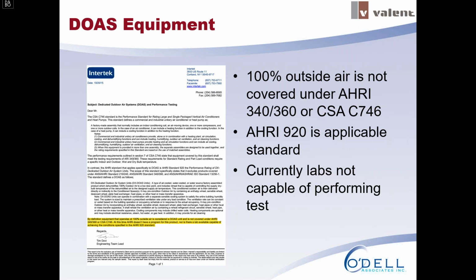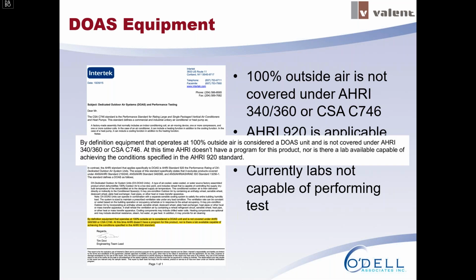The engineering team lead for Intertek came back to us and identified that a 100% outside air unit is considered DOAS and is not covered under AHRI standard 340-360. He also confirmed that the labs were not capable of testing DOAS units to the current standard, AHRI 920. So right now we need to use the testing, standards and efficiencies given under the other AHRI standards and codes that are in place for units with recirc air on them. So just an interesting comment on where we're at as far as testing and standards today with DOAS equipment.